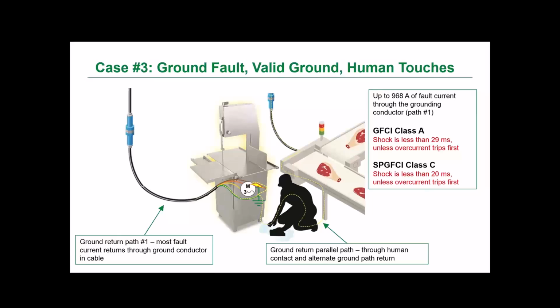So the Class A GFCI would respond in approximately 29 milliseconds. So that's based on that maximum trip value in the standard of the time equal to 20 over the current to the power of 1.43. The Class C special purpose GFCI will respond slightly faster at 20 milliseconds, because that is the maximum value specified for all faults above 300 milliamps.